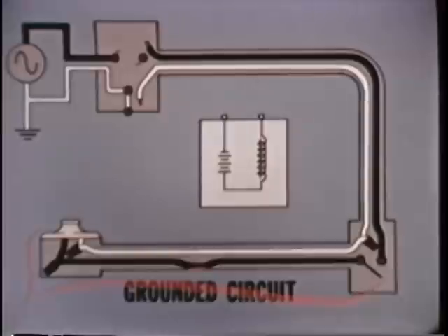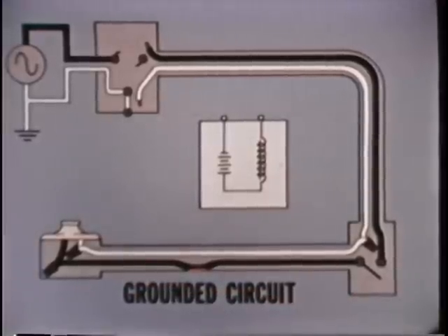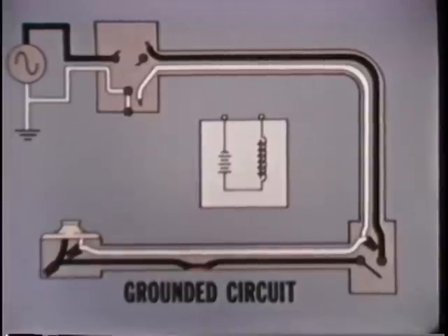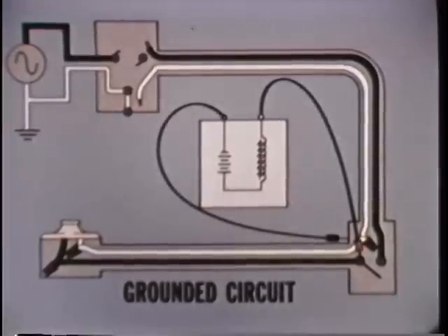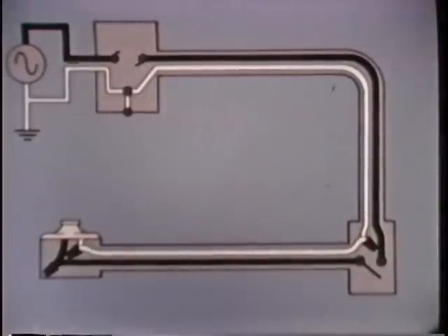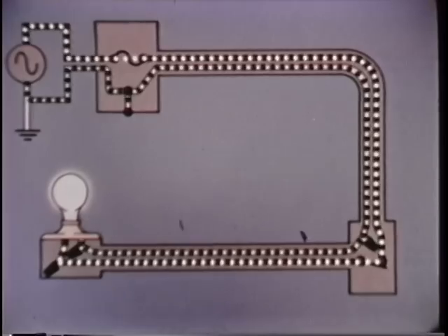In a longer circuit, the diagnosis would be confirmed by checking the next connection. The ground is removed, and the circuit is retested at the trouble point. And all connections are restored. The light and fuse are replaced, and when the switch is turned on, the circuit is back in service.